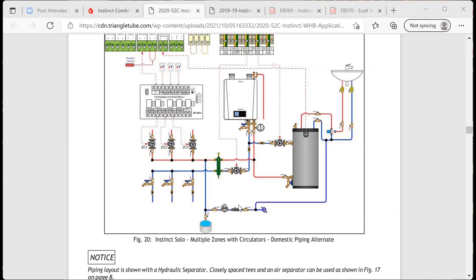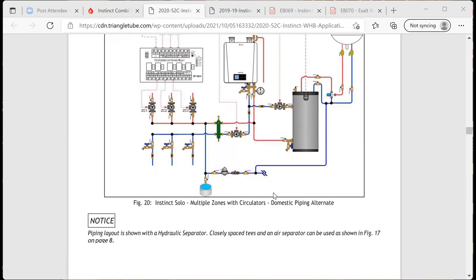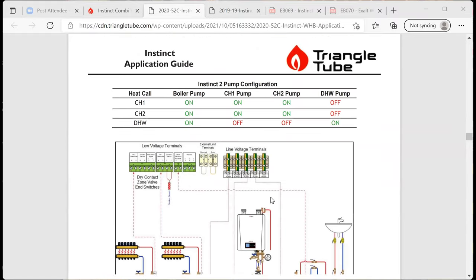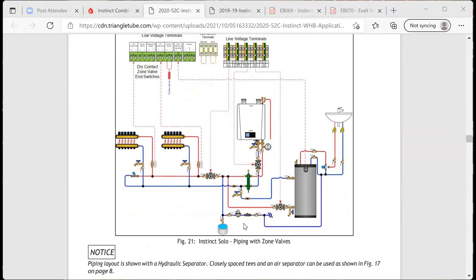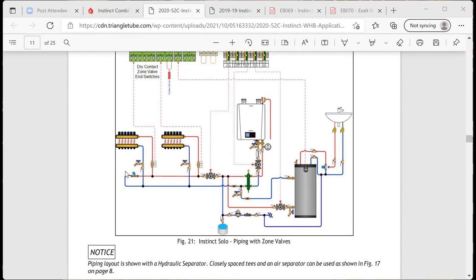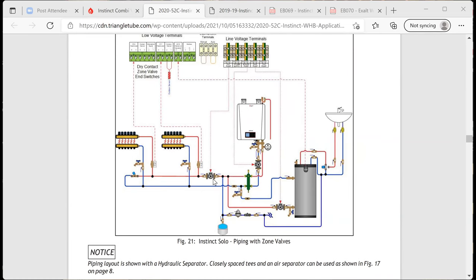That's one I see get messed up quite a bit. Let me go down. This is showing indirect and secondary with us using, let's say, the Taco 0018, and we pressure balance it with the radiant balance. Well, we got a pressure balancing valve here, which is the best way to do it. But if you don't want to use the pressure balancing valve and tie your supply into the return header, that 0018E Taco pump is a great pump because you can use a Bluetooth app and set your GPM with it.